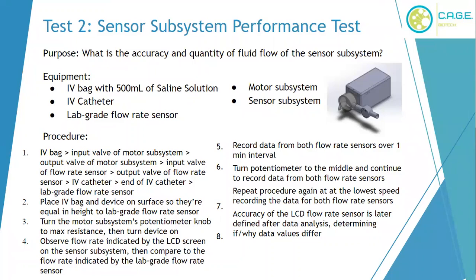The potentiometer is turned up to max resistance so the motor is at the lowest RPM, and when the device is turned on, both the flow rate sensor on the sensor subsystem LCD screen and the lab-grade flow rate sensor can be compared. Data from both sensors is recorded over 1 minute, and trials are repeated by turning the potentiometer down by 1 increment each time. This is repeated until the potentiometer reaches the least resistance or the motor subsystem fails by dripping fluid or delivering fluid inconsistently. Consistency is defined more accurately during the data analysis portion.